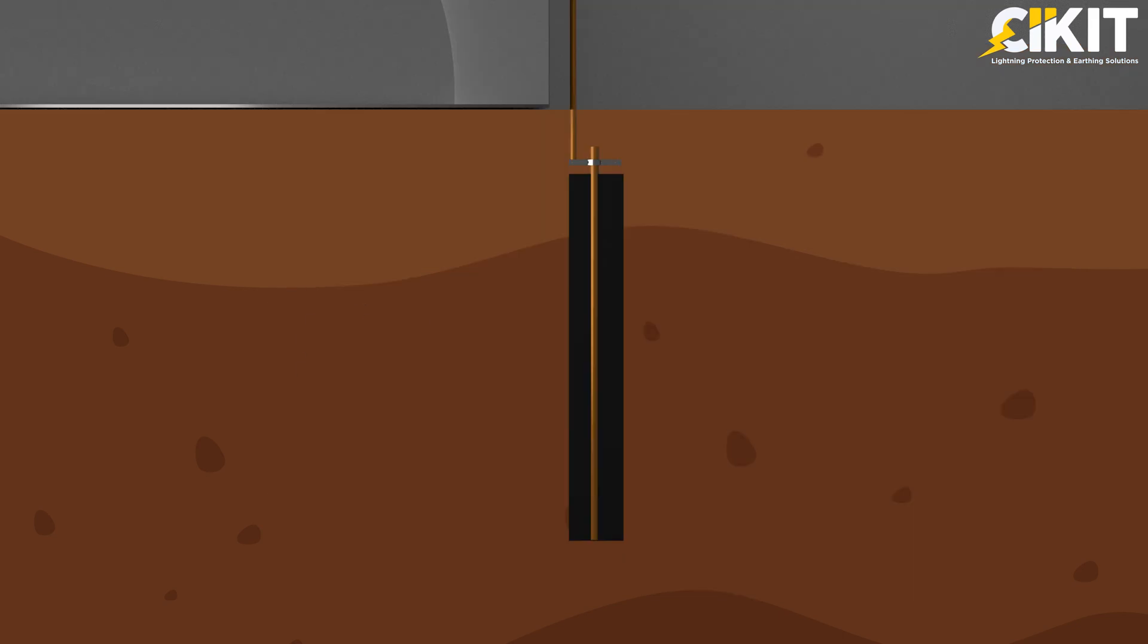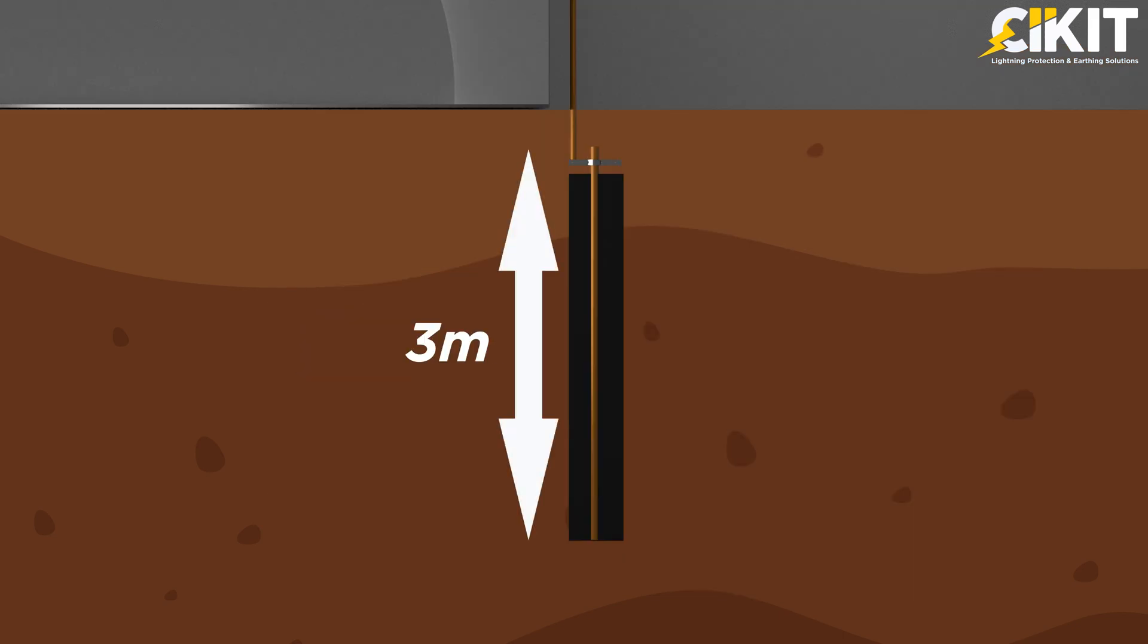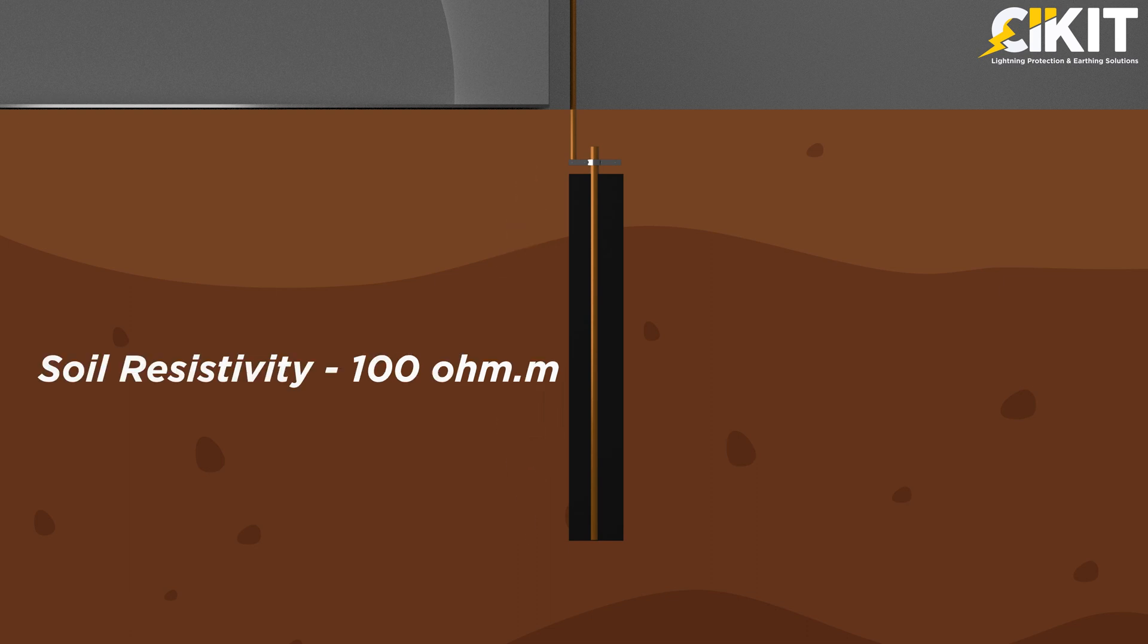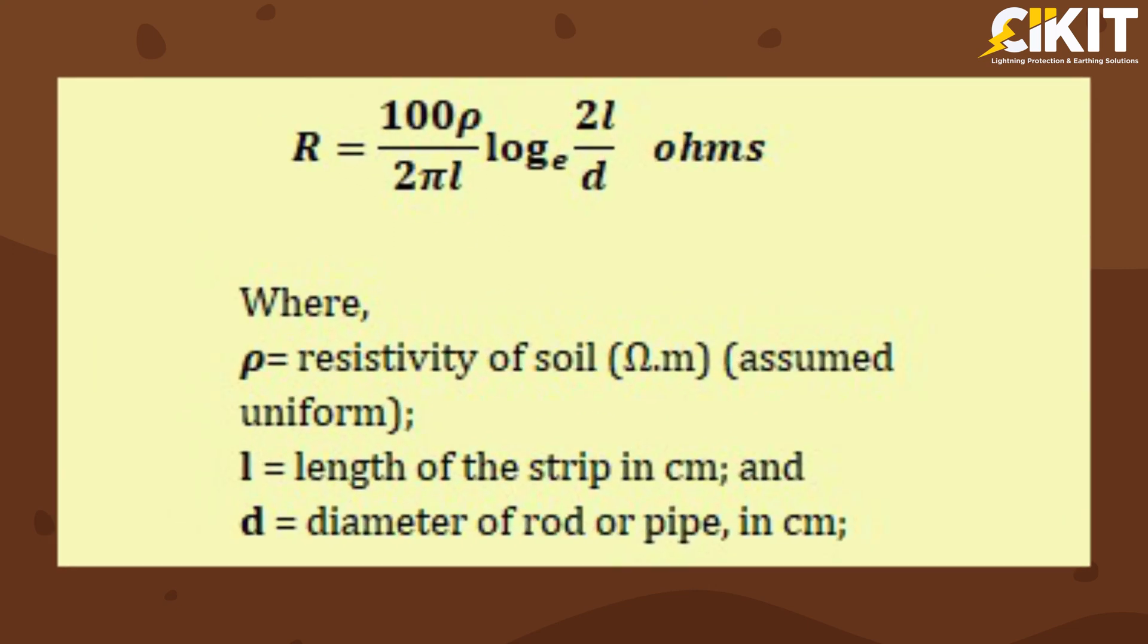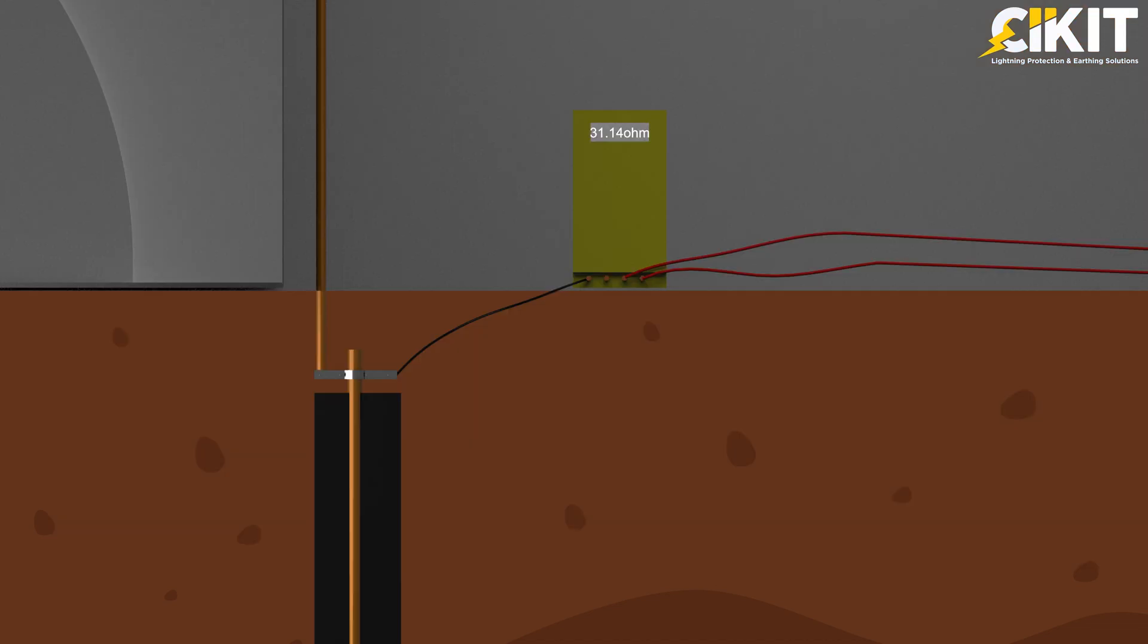For example, a 17-millimeter diameter and 3-meter-long earth electrode and the resistivity of the soil be 100-ohm-meter. IS-3043 has given the formula for calculating individual earth electrode resistance. The individual resistance of the considered earth electrode comes to 31.14-ohm.